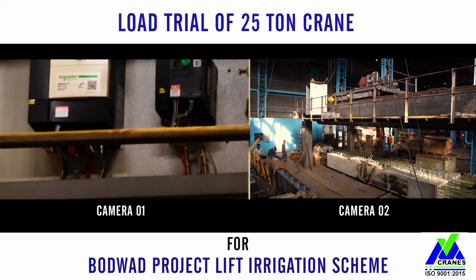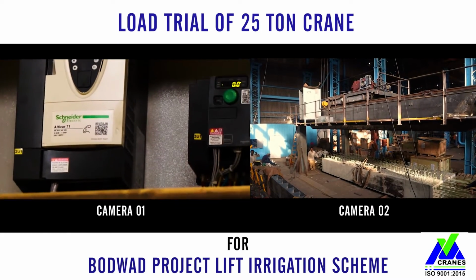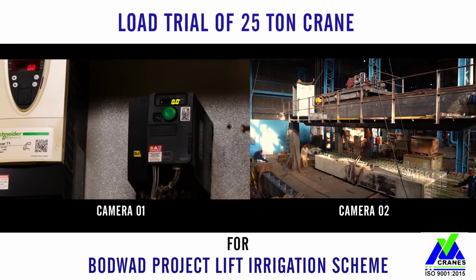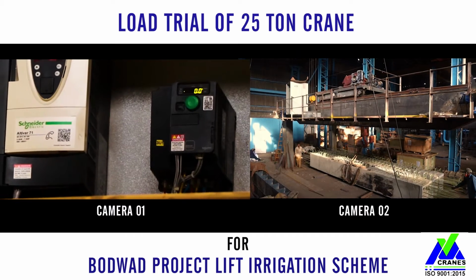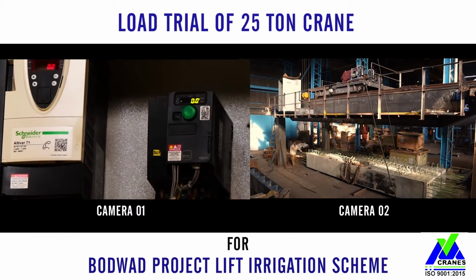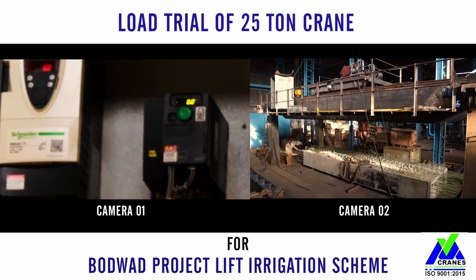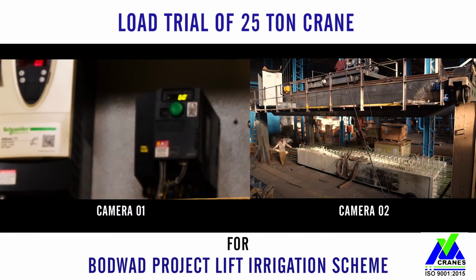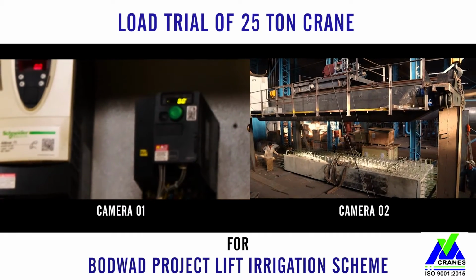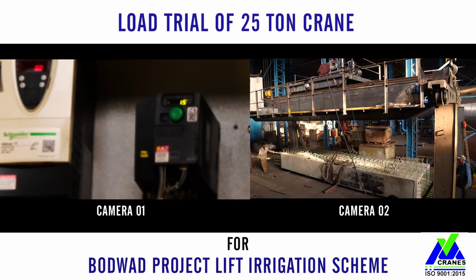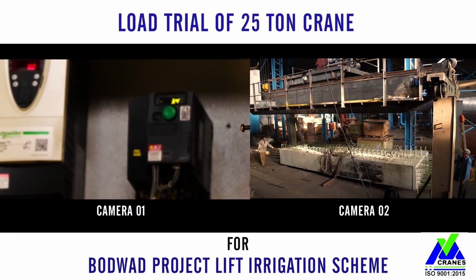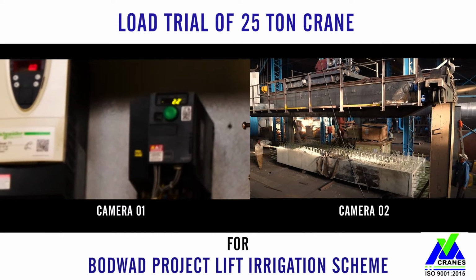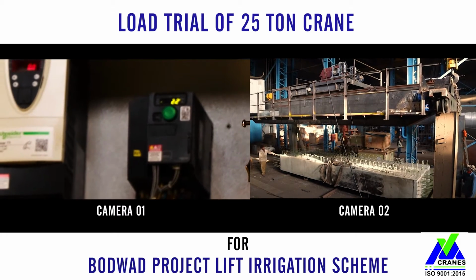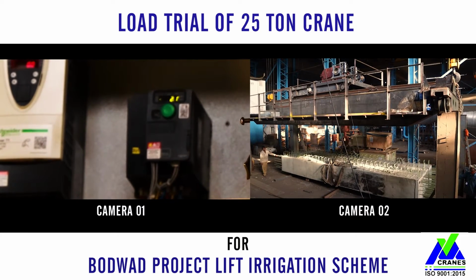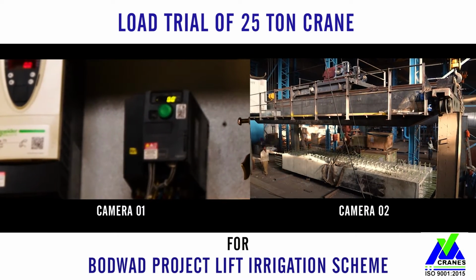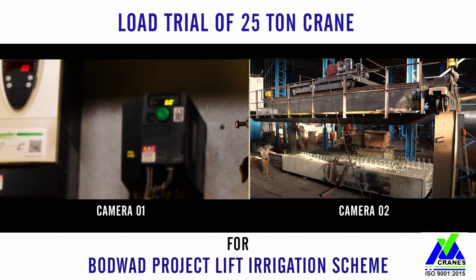And now we are going to move the load in the cross travel direction. So the current on the cross travel also will be displayed on the VFD. The first VFD is the main hoist VFD, the second one is the auxiliary hoist VFD, and the third one is the cross travel VFD. Now the load is being moved.